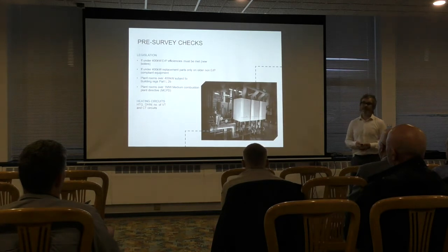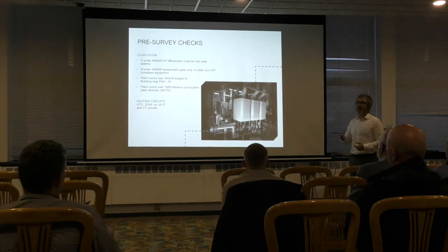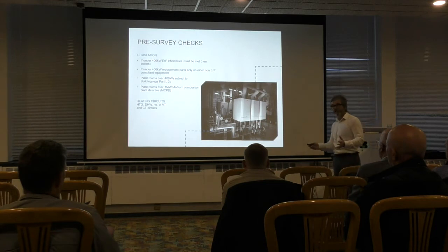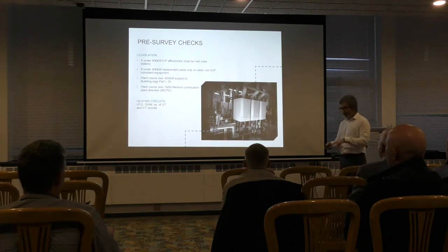And it throws up all sorts of arguments as well, because this happened to me last year, where a consultant engineer phoned me and said, I've got this project, we're replacing 2 150 kilowatt floor standing boilers. He said, I've already decided what I'm going to put in. I've done my drawings, can you come and see me just to do a sanity check, just to make sure I've done everything right? I went in to see him. He'd probably picked out of his library an ideal commercial brochure, probably dating back to the early 90s, and picked out an old atmospheric boiler that we don't even manufacture anymore, and decided he was going to put that into his project.